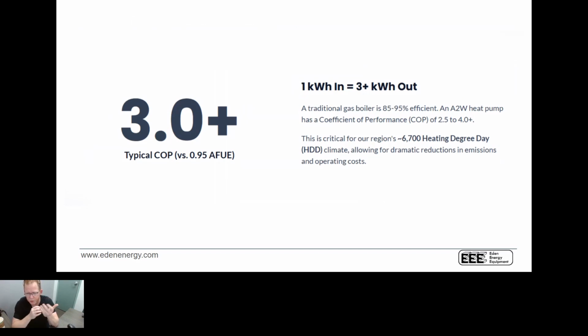So if you compare that to a typical gas system, you're going to be about 320% efficient, because on paper, a condensing gas boiler is typically going to be 95, 96% efficient. So the real beauty of a hydronic heat pump is the ability for the COP to result in better comfort with reduced operating costs, with obviously a few caveats. So with the heat pump, whether it's air to air, air to water, water to water, water to air, there's a lot of different configurations. COP is king. And one of the really distinct advantages about an air-to-water system is we have a lot of control over what that COP can be.